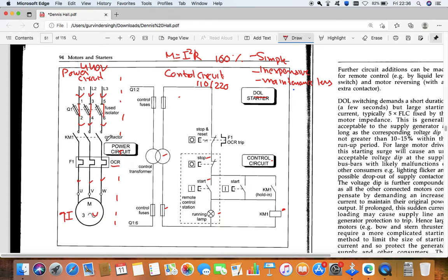For making this, the contactor relay is in the control circuit. So I need to energize this KM1. Okay, so let me show you, this control circuit is taking supply from the power circuit. Okay, here, and one from here. So here up to here it is 440 volt, and then it has a step down transformer that will reduce the voltage to 110. Now the control circuit has 110 voltage.